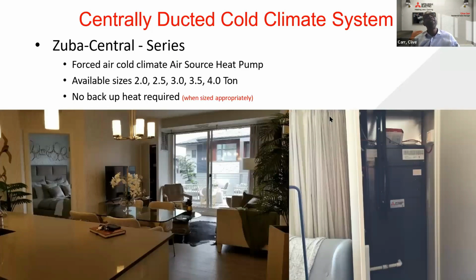So we see more of an illustration of the application. We take a look at our ducted model. In this application, this was an air handling unit or cold climate heat pump system that's been used to provide heating and cooling. And in some projects that we've done, we've also used it just for cooling and integrated it with a secondary heating source and used one thermostat to control both systems. So it does provide you the flexibility, again, for a hybrid approach or an all-electric approach.